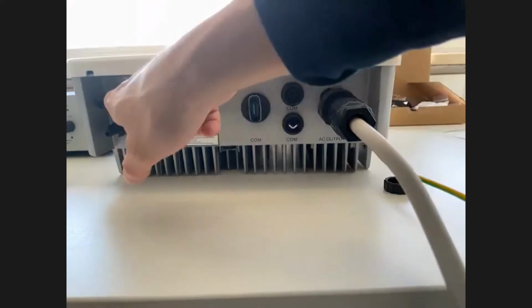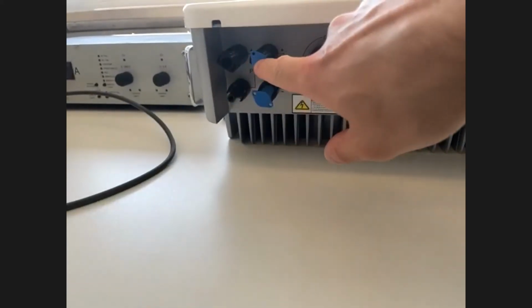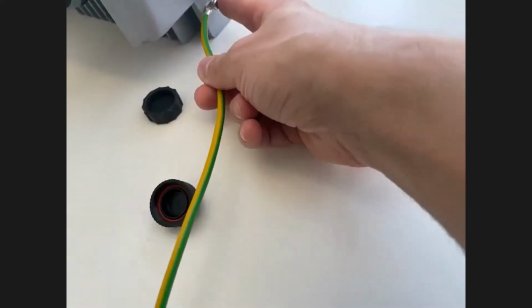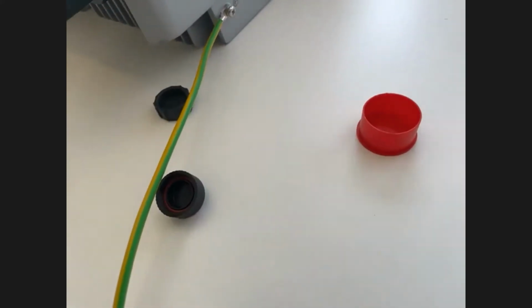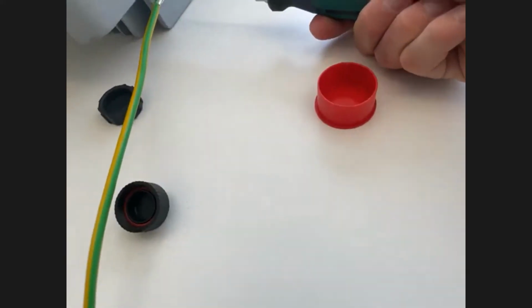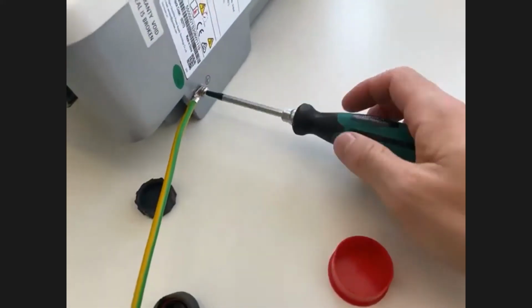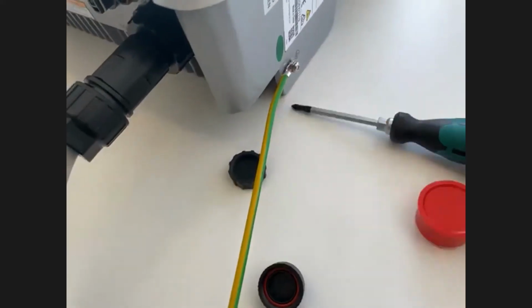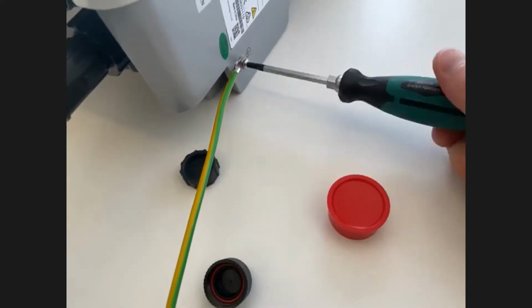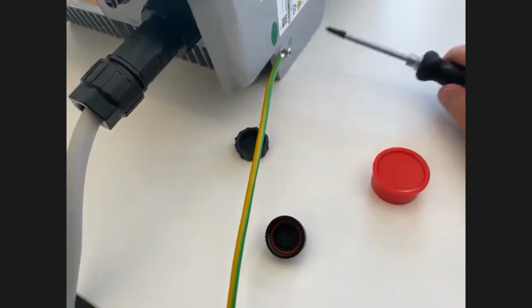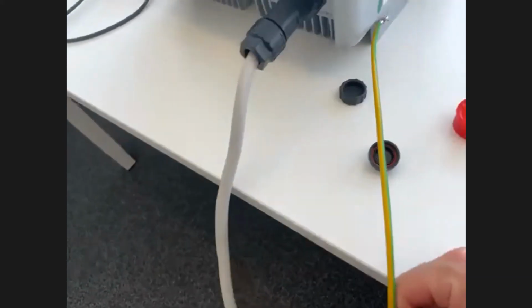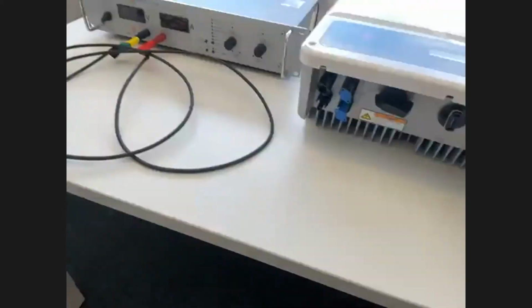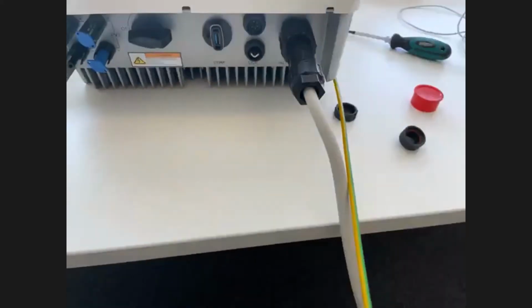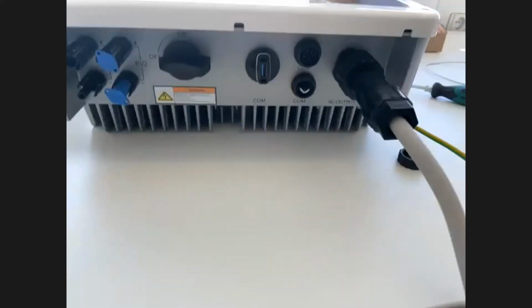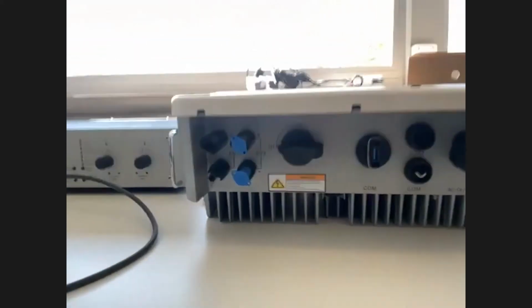Secondly, you connect the DC side here, you have the PV inputs there. But before doing that, you should connect the PE cable here that's located on the side. And that's basically just a screw that's tightened here. And then you have the PE cable. And make sure that you have the correct size of the cable so that it's safe. When the PE is connected and AC is connected, then you can connect the DC inputs.